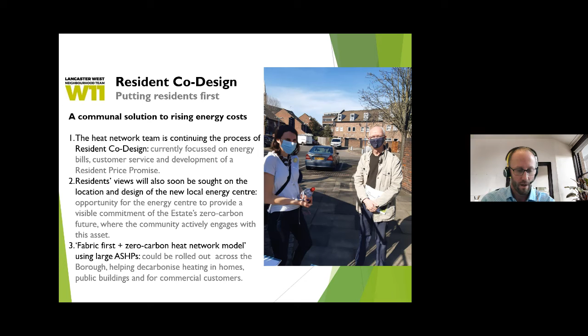In terms of how we're going to make zero carbon happen, we're not blessed with any energy from waste plants, and we haven't got any industrial waste heat. So we knew from the start we had to consider environmental sources of heat, and we tested 3 options. Our preferred option for this core scheme is a large air source heat pump with an electric boiler. It works well for the scale we're at, we haven't got any cooling requirements, it's free at point of access, and we haven't had to develop a heat supply agreement. We've proved it's technically and economically viable.